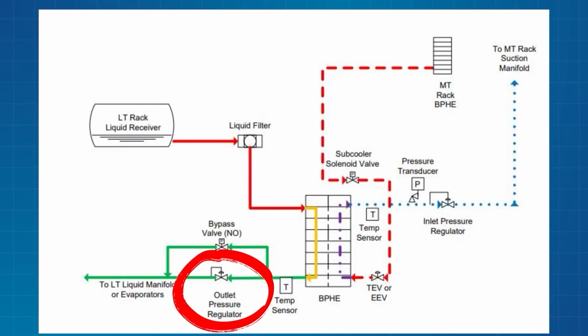Okay? Well, this valve, this outlet pressure regulator, is lowering that pressure. It's making my valve smaller because the pressure differential is less than it would be without it. Does this make sense? Everybody with me? Doesn't sound like a good idea at all, right? Sounds kind of backwards. Isn't that the opposite of what we're trying to do with the subcooler?